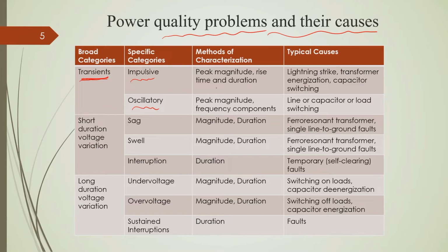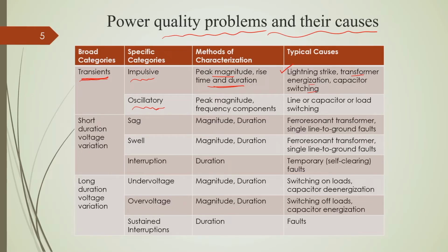Basically, impulsive transients we characterize based upon peak voltage magnitude, rise time and duration. The typical causes of impulsive transients are lightning strikes. Lightning is one of the reasons for this type of power quality problem. Transformer energization and capacitor energization or capacitor switching create another sort of transient. Similarly, oscillatory transients we characterize based upon peak magnitude and frequency component.